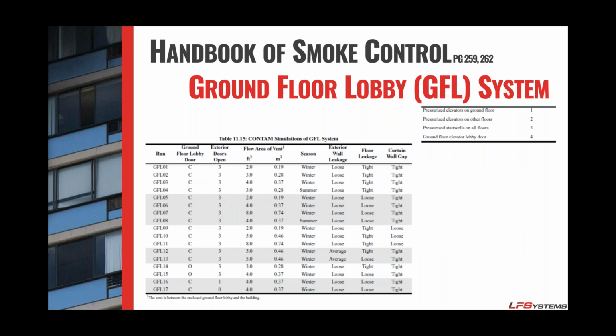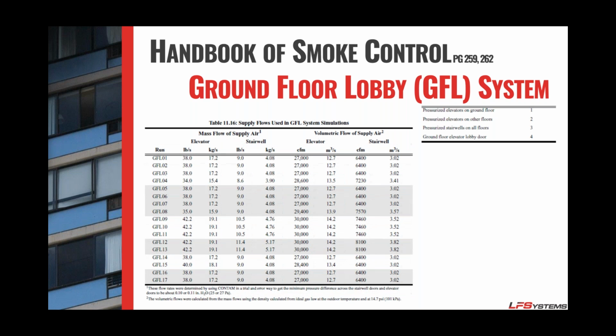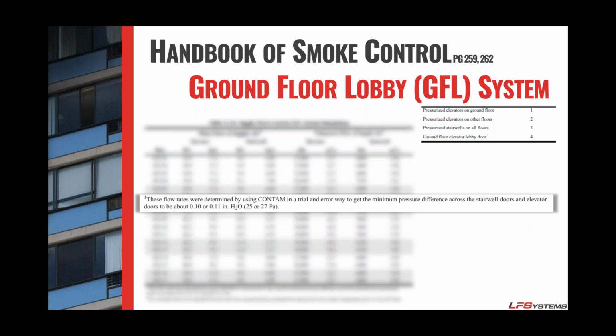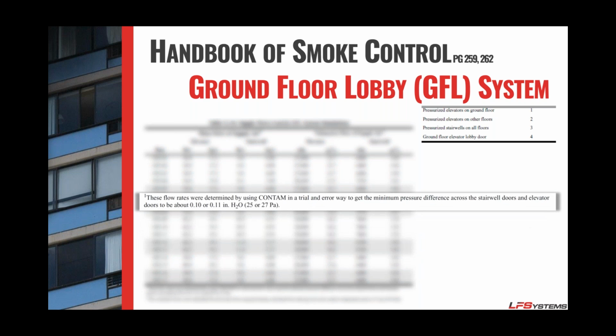17 different scenarios were run for the GFL system, and that's different conditions, different vent sizing, different conditions with the lobby doors. And as you can see, lots of different CFM variances based on those conditions. One thing to note, note 1 says these flow rates, let me see if I can pull this up here. There we go. These flow rates were determined by using CONTAM in a trial and error way to get the minimum pressure across the stairwell and elevator doors to be about 0.1 to 0.11 in H2O. So basically, it's just keep trying until you get it right in your modeling.